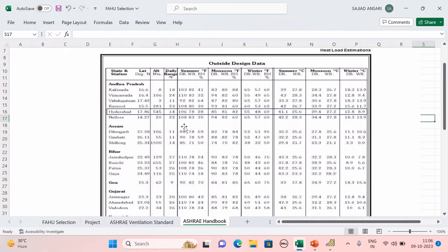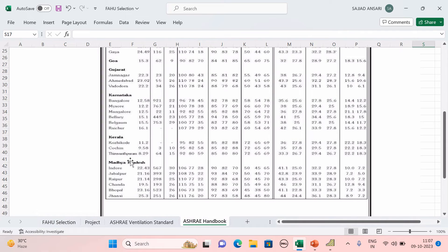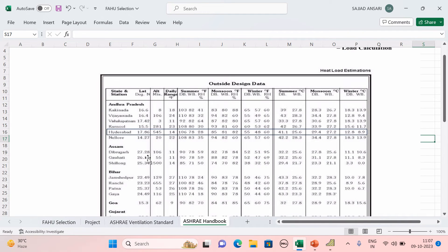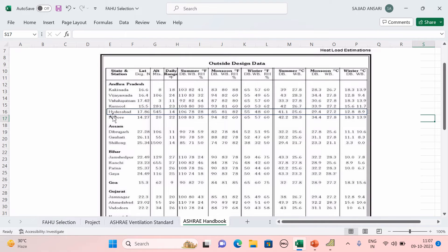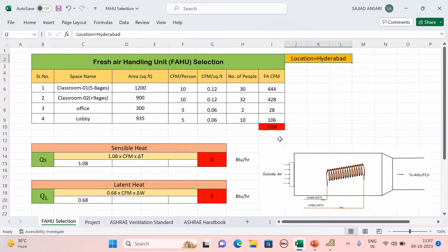This value comes from the ASHRAE Handbook under Climatic Design Data. For your state and station — I am designing for Hyderabad, Andhra Pradesh. In summer season the dry bulb temperature is 106°F, wet bulb is 78°F, and outside relative humidity is 28%. So the air entering the AHU is at 106°F.